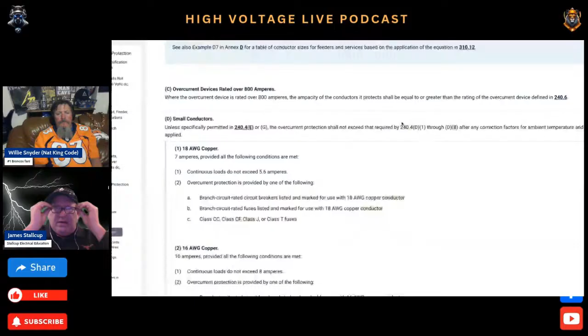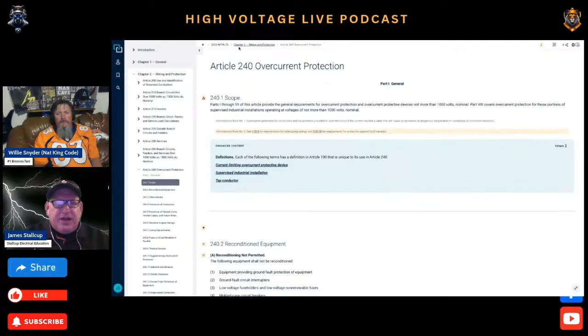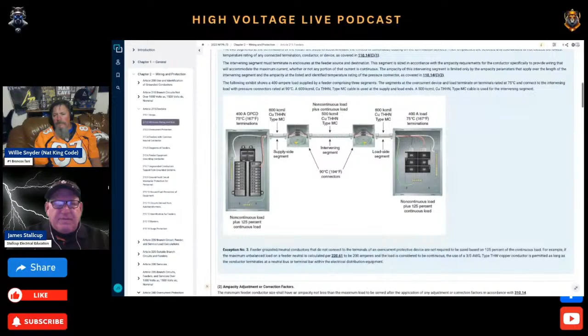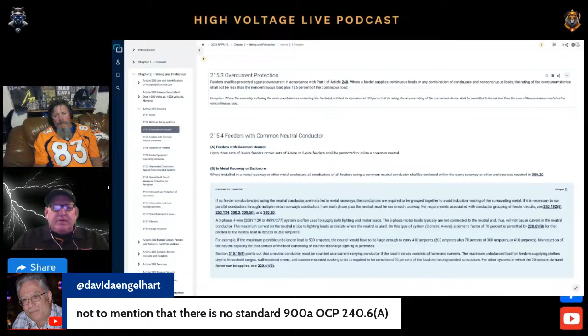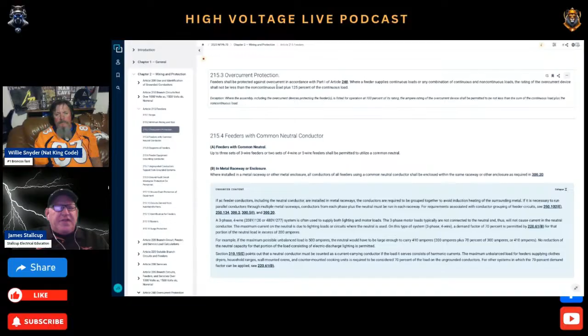Okay, now we've looked at 240.4(C). Now, what I want to go into is he was looking at 215.3. Let's take a look at it. When you pick up 215.3, what does it say here? Feeders shall be protected against overcurrent in accordance with what? Part 1 of Article 240. Yeah, and David does bring up a good point that there's not a standard 900 amp overcurrent device, but that doesn't mean that it makes the question wrong. If you're able to purchase a 900 amp overcurrent device, then you can. Just go pull it up on Google, and you'll see you can purchase a 900 amp. But the point is, it says feeders shall be protected against overcurrent in accordance with Part 1 of Article 240.